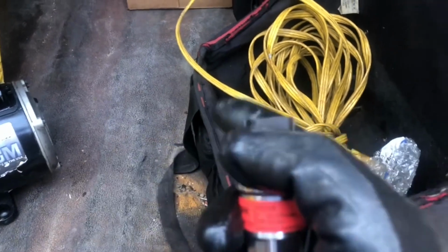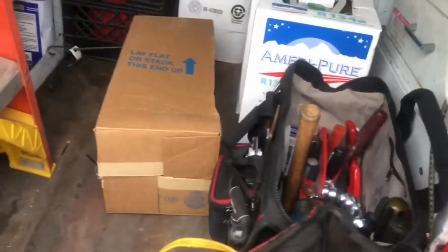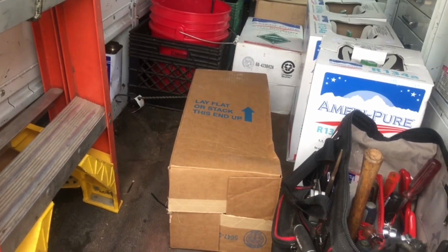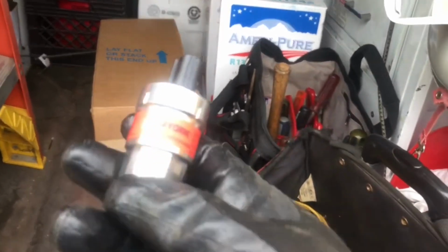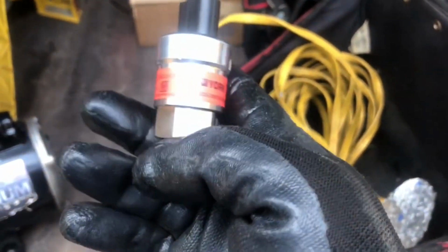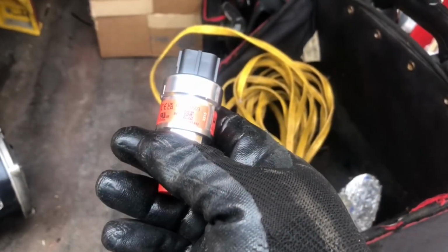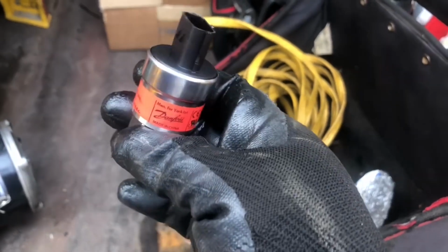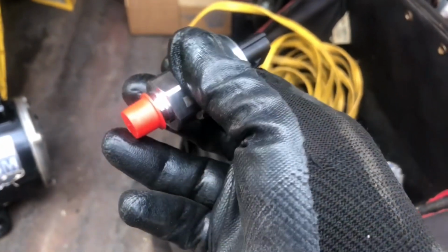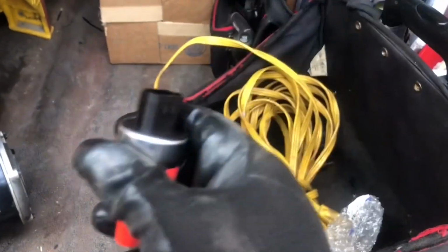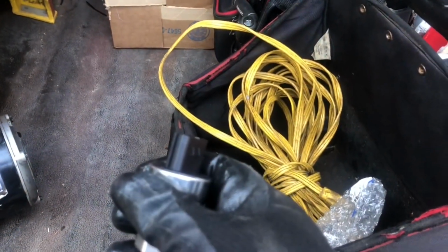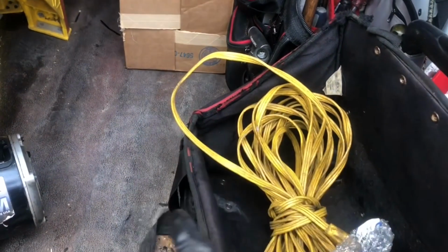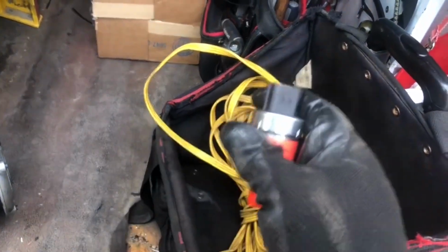Once again, what I'm gonna do right now is I'm gonna recover, not recover without a vacuum pump. I'm gonna recover the refrigerant out of the condenser, not condenser, but out of the compressor, to lower my pressure there. But still, if you're gonna be doing this type of job, whenever you take out this transducer, still do it slowly. Kind of use a rag around, because you might still have a little pressure trapped somewhere, and it's gonna spill some oil out of there. Always check your gauge in the back of the oil housing, wherever I place the small gauge. Make sure the pressure is either zero or I'm on zero.